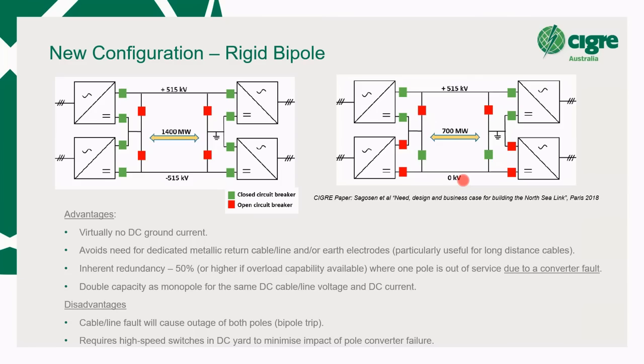The next question we had was in regards to your brief summary on LCC technologies, and it was, what is considered as a high short circuit ratio for LCC? The rule of thumb is about 2. But as with everything, everything depends. So you would have to do your studies, but the rule of thumb I've used in the past has been, if you need less than two, then I'm almost always focusing in on the VSC solution.